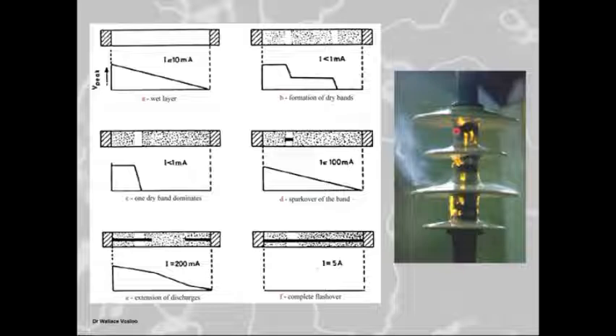And then this arc will go from the surface out into the air, and you find that it will finally lead to the full breakdown or full flashover of this insulator from live to dead end, okay? And it's all driven by your current levels, different current levels. And you'll see that here on this surface, this is the moisture evaporating off as it's starting to dry out the surface.